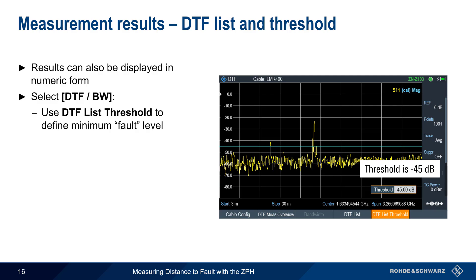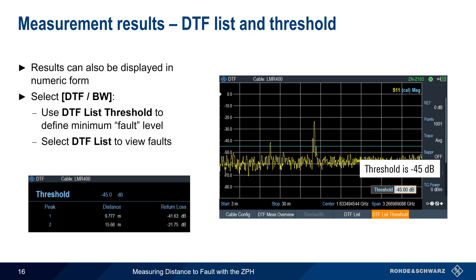Distance to fault measurements can also be displayed in numeric or tabular form. This is done by using the DTF Bandwidth hard key. First, use DTF Threshold to define the minimum level, in dB, that should be considered a fault. In this case we've chosen minus 45 dB, and this threshold is shown on the display as a blue horizontal line. If DTF List is then selected, a table showing peak number, distance, and return loss is displayed. Here we see two peaks: one at 9.8 meters with a return loss of about 42 dB, and the second at 15.7 meters with a return loss of about 22 dB.